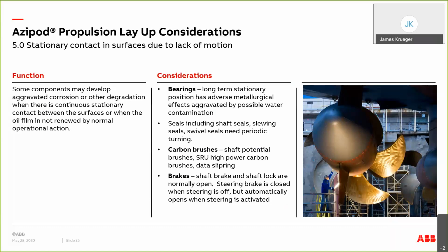Seal systems, of course, must be exercised. What happens with the seals is most seals need some type of lubrication in order to properly slide on the surface with which they meet. And if the oil or water that happens to be lubricating that seal hasn't been exercised into the seal surface in quite some time, then the seal almost welds itself to the surface. In that case, when you first turn, even microscopically little pieces of the seal lip will pull away and lead to eventual seal failure. In extreme cases, it can be almost immediate, where the seal tears itself if it's been stuck to the surface for too long.